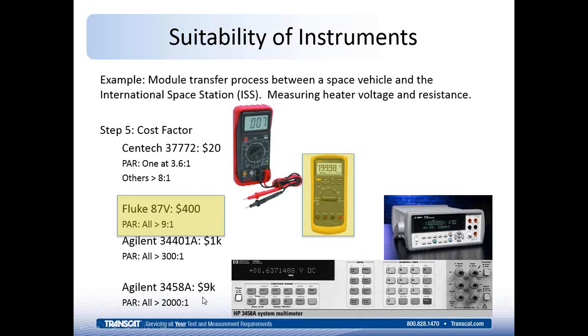So after you become comfortable with the PAR and you use that a little bit, that's a very simplistic way of getting ratios into place that say whether an instrument has too low of a ratio or way too high of a ratio, but whether it's acceptable or not. Then you want to take it a step further, because when you're looking at the accuracy of the instrument and you're taking a look at making those measurements in the process, there are other factors that come into play that can cause errors in the reading.